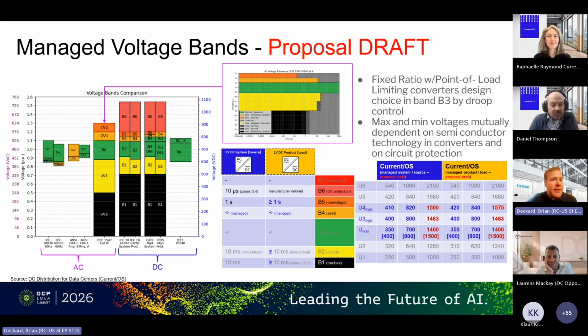If you notice in here, there's derating possible for lower voltages, say, for example, less than 760 volts as a starting point. What is also important to consider is that line losses have previously been handled differently for the required voltage operation range for sources versus loads. That's preserved on the low side and now introduced on the high side because we run so close to the maximum possible voltage. And then here, as you can see, there's an effort to look not just at 800 volts, but how this may scale into the future with 1500 volts, and where we may need to consider exactly what the rules are for how we abide within the low voltage limit.